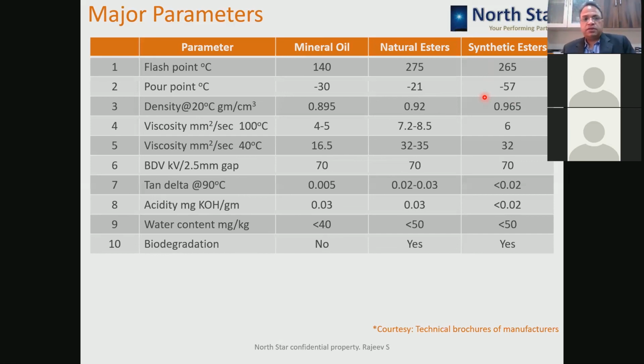So the cooling properties of synthetic esters at sub-zero temperature are best. Density: mineral oil is 0.895, natural ester 0.92, and synthetic ester is 0.965. So density-wise, mineral oils are best. They are less dense, so they are lighter as compared to natural and synthetic ester. Viscosity, again: mineral oil is 4 to 5 at 100 degrees centigrade. Natural esters are 7.2 to 8.5, and synthetic esters are 6. So natural esters are most viscous compared to synthetic and mineral oil.